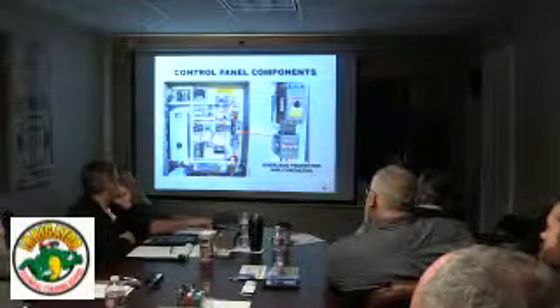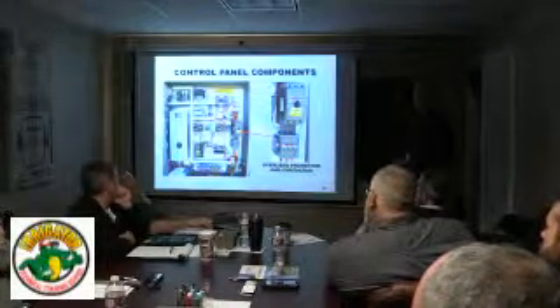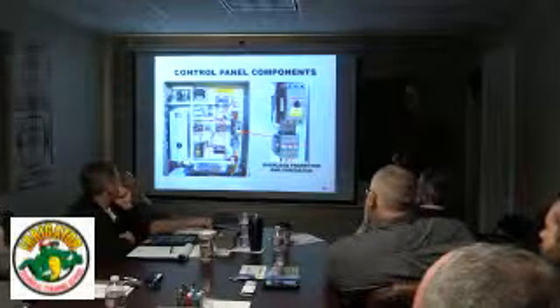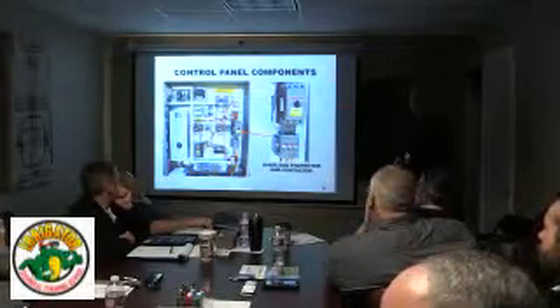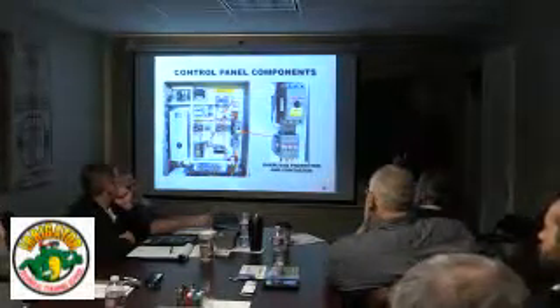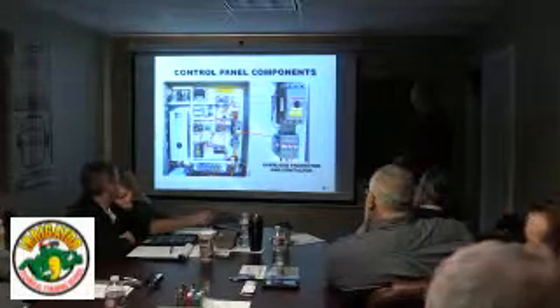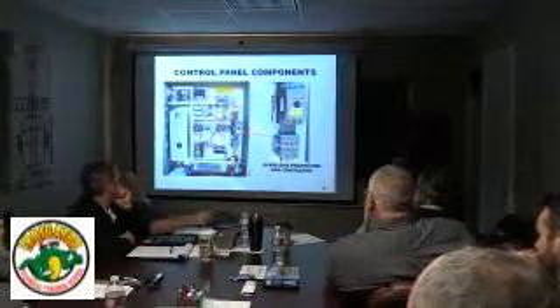A lot of times it helps protect it. If you get real fast power surges or transients, it may not be quick enough to protect the drive, but it'll prevent it from running on too low voltage for too long.